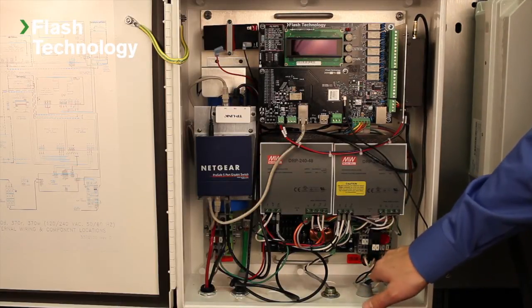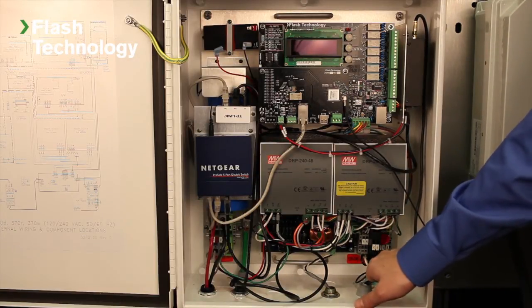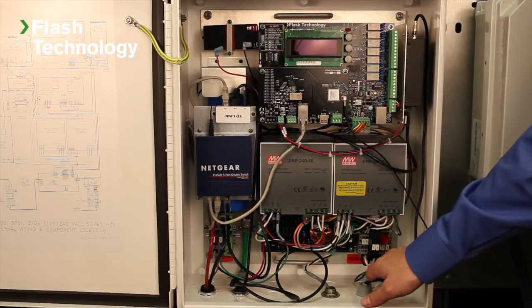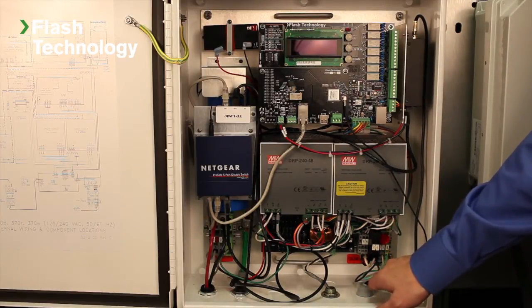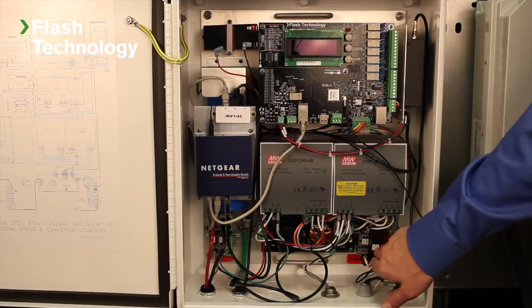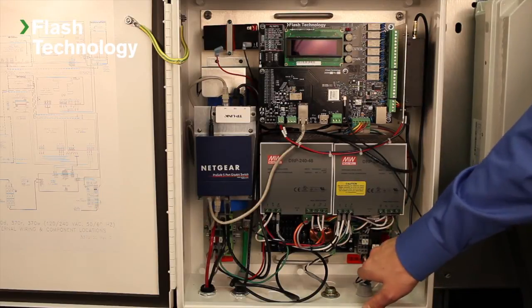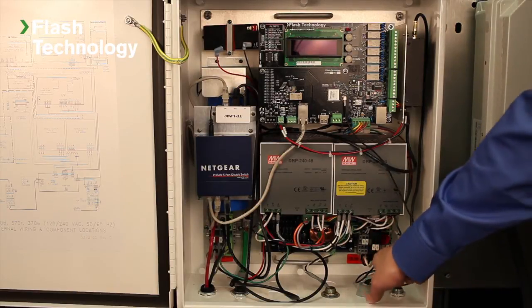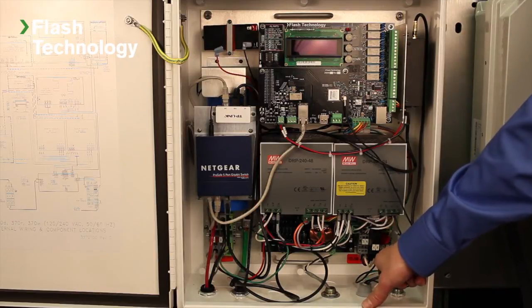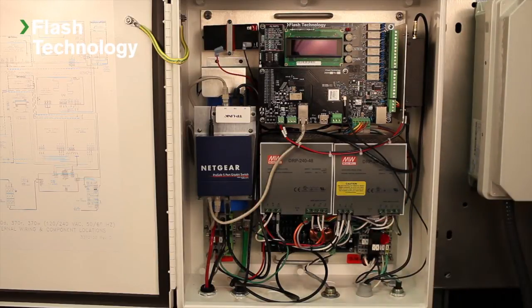The power requirement for a Vanguard controller is 120 to 240 volts AC, 50 to 60 hertz. Now the power is going to be wired directly to the right of our fused insert, the F1 and F2 fuse block. We'll connect our power directly to the L1, L2, and grounding connection points.